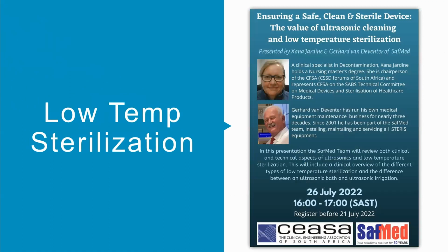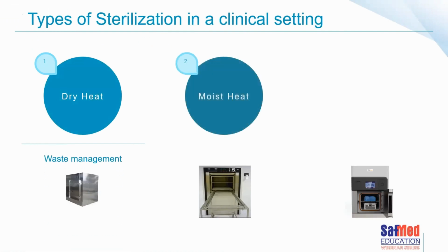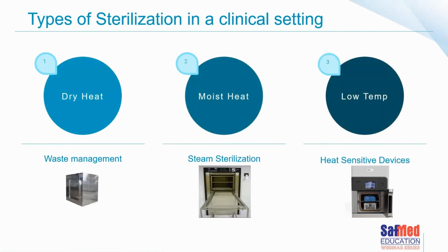Okay, so we've covered ultrasonic cleaning. Now to go into a little bit more about low temperature sterilization as a principle, as a concept. Just as a reminder, of course, different types of sterilization that we will find in the clinical setting. Dry heat we tend to find in waste management environment, not really in the clinical setting. Moist heat, generally steam sterilization, as you know it, most cost effective, most common, and used for standard surgical instrumentation, linen, bowl packs, those kind of devices. And then low temperature sterilization modalities, and they are there for heat and moisture sensitive devices.